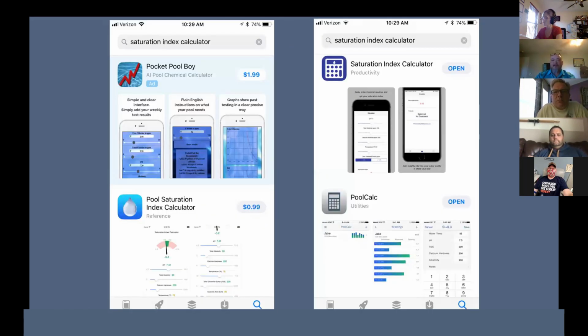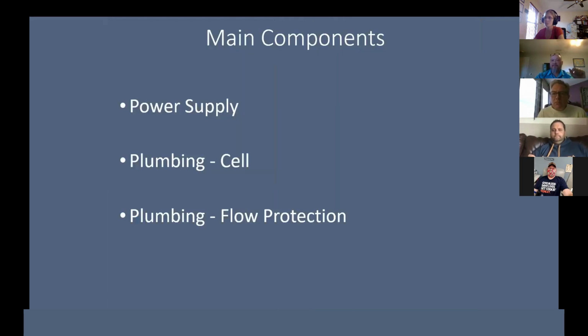And then again, you can go online and download a couple of apps, 99 cents for an app. There are some of them that are free. I think most of the apps you'll see now are going to be free apps. They're real easy to use. Just test your water, plug the numbers in, and it'll tell you if your water chemistry is balanced or not. The one thing that I do recommend is when you're taking your tests, don't use test strips, because test strips don't give you quite the right parts per million results that you need in order to calculate your saturation index.